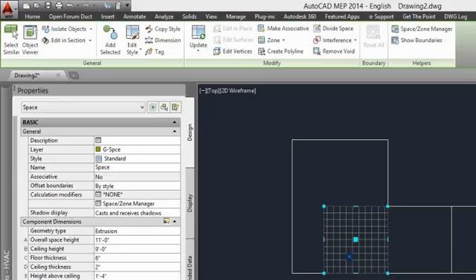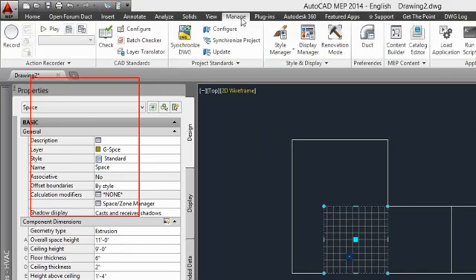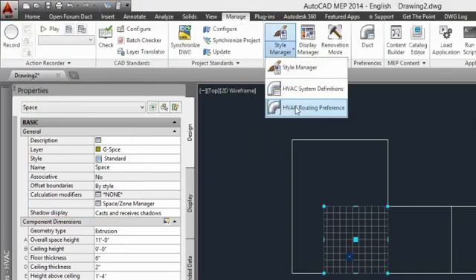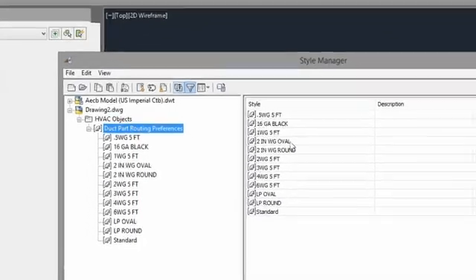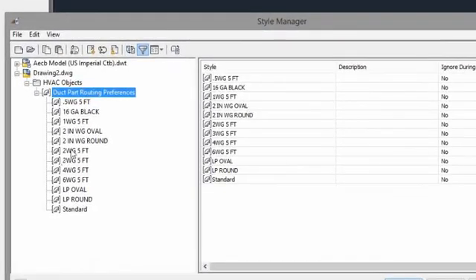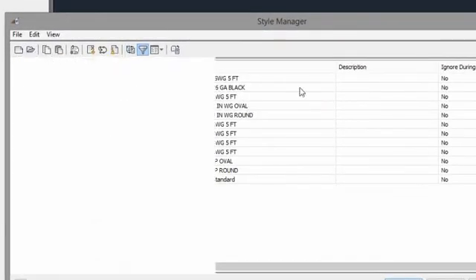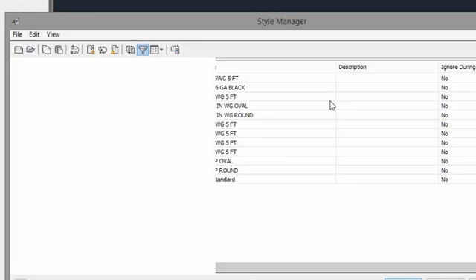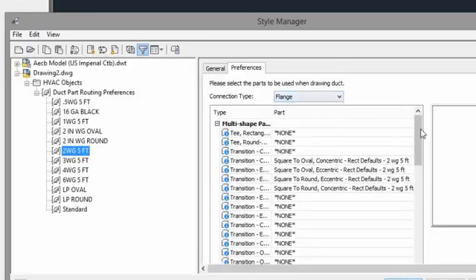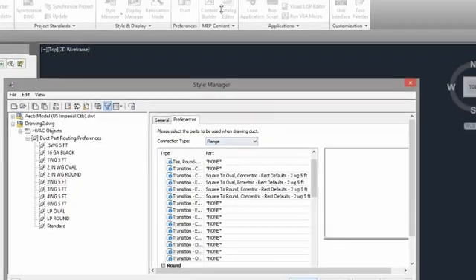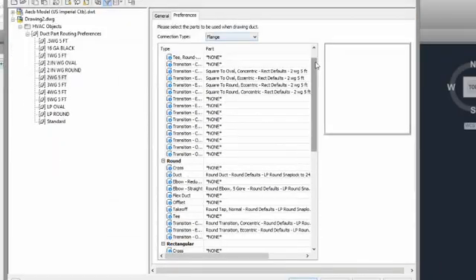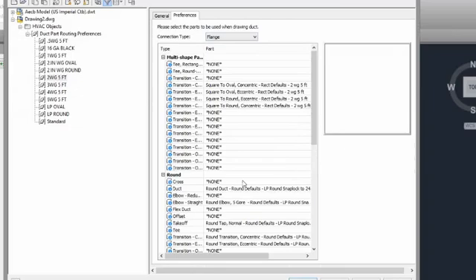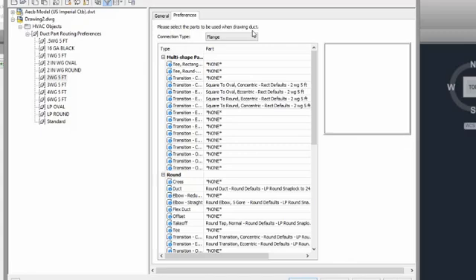So let's look at the Style Manager in AutoCAD MEP. So I'm going to go to the Manage tab, Style Manager dropdown, HVAC routing preferences. I'm going to select one. When I select it, it's going to take just a couple minutes to pop up. The reason being for the little delay is that when we select the routing preference, it's got to go into your database and query all of the currently loaded parts in your catalog to generate a list for us to set for our routing preference. So you can see a flange. That is the connection type that you must have in order to see the East Coast fittings. If you have your catalog loaded and you come into the routing preference and you do not see these fittings, then usually the culprit is this is not set to flange.